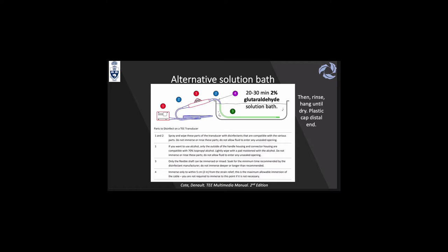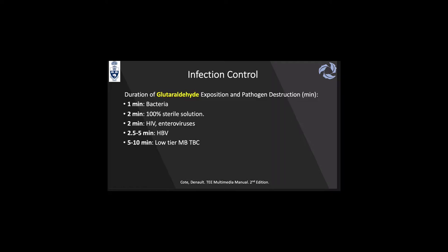Why is 20 minutes so important, and can we shorten it in an emergency? Under glutaraldehyde exposure, pathogen destruction happens as follows: within the first minute all bacteria are gone; at two minutes you achieve 100% sterility and kill HIV and enteroviruses; up to five minutes is needed to kill hepatitis B virus; and a maximum of 10 minutes is needed to reach a very low titer of Mycobacterium tuberculosis. That is why it is so important to keep the probe in for 20 minutes to ensure a completely sterile probe.